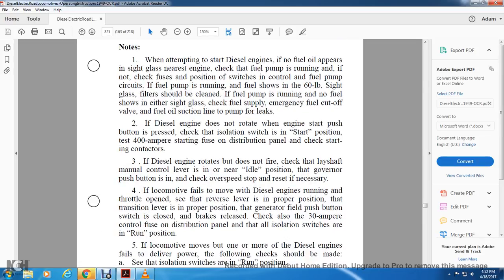2. If the diesel engine does not rotate when the engine start push button is pressed, check that the isolation switch is in the start position, test the 400 amp starting fuse on the distribution panel, and check the starting contactors. If the diesel engine rotates but does not fire, check that the lay shaft manual control lever is in or near idle position and that the governor push button is in. Check the overspeed stop and reset if necessary.